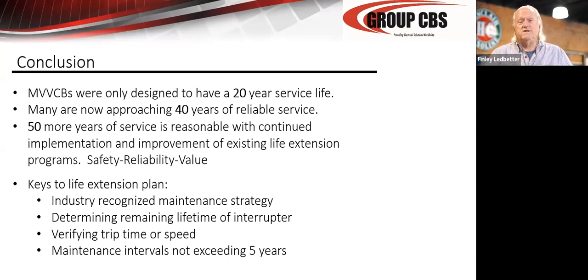Because you think it's expensive and difficult to replace the switchgear, try to replace 2 miles of armored cable or buried cable in your plant. Now you're talking about real money and real downtime. So be very careful of disturbing these cables, especially older cables, if you do have to go in and remove the switchgear. Many of these breakers are approaching 40 years old. We're going to have 50 more years of service out of them.